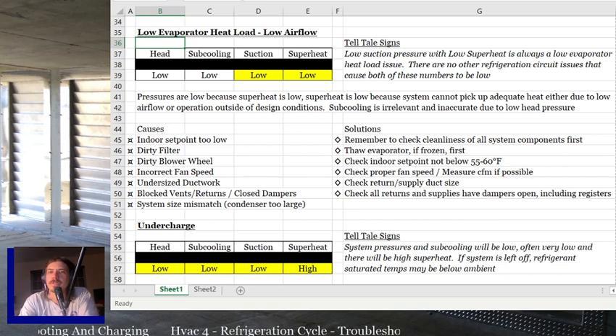Because our head pressure is low, you're probably going to have low subcooling, but if you've got low evaporator heat load and it's hot outside, you might have normal to high subcooling. It's hard to tell sometimes. But it's irrelevant. It doesn't matter.